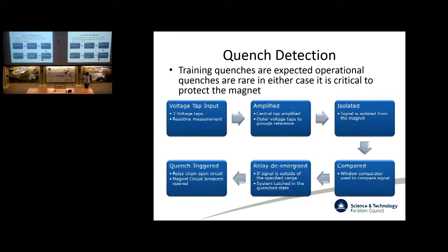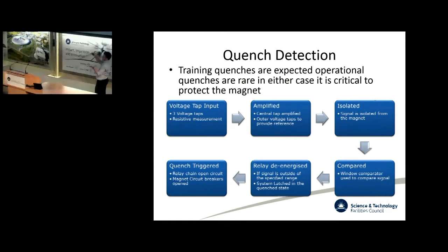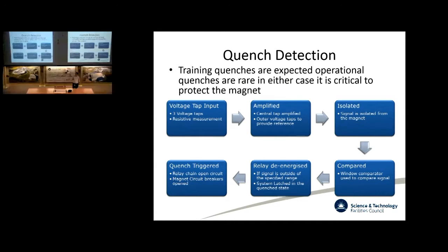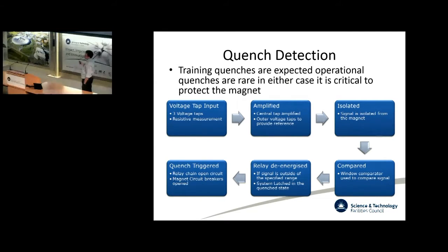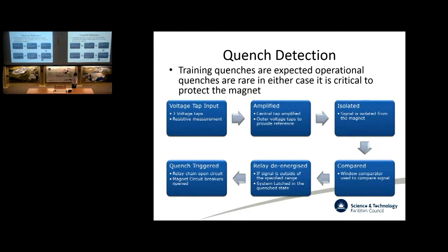Then we go to a window comparator, which basically, if the signal is outside of a certain range, in this case about 4.5 volts, then it will de-energize these relays. Once these relays are de-energized, that's essentially the start of a quench being detected. That then carries on to open up contactors that separate the power supply from the magnet, so that we're taking away the power source from the magnet. The magnet is then allowed to discharge its energy through a dump resistor, and the whole process from quench to detection and opening those contactors takes about 100 milliseconds, and then the whole process of the magnet dumping its energy is in the order of about maybe 20 or 30 seconds.